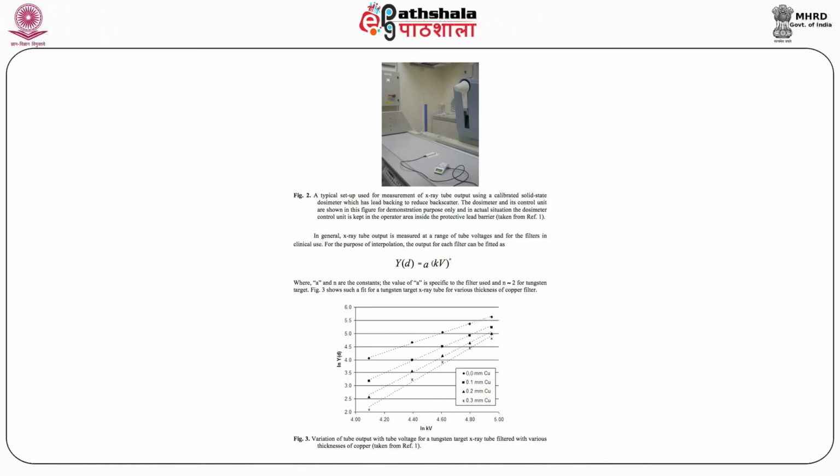The consistency means if I measure the output of the machine today with a given setup of the machine, it should be valid for tomorrow or even the day after tomorrow or many subsequent days when this machine is used for a similar setup of the operating parameters.